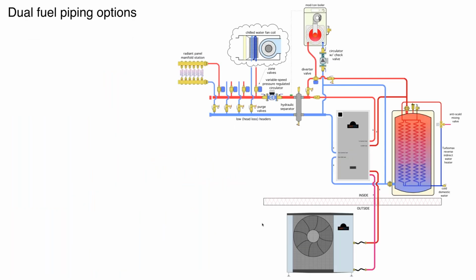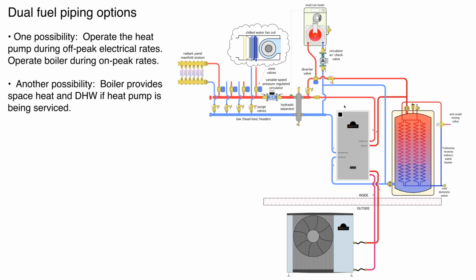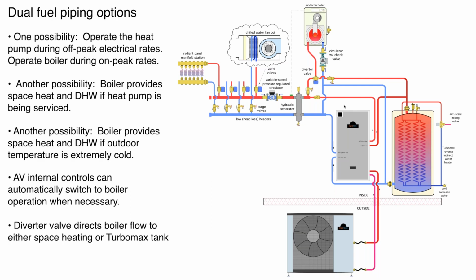Okay. Dual fuel. You can tie a boiler in with the heat pump. There are several ways to do it. I'll just go to the next slide, but first let's talk about these. Where do you want dual fuel? Well, you might have an existing boiler, or you might want something that could operate in a power outage where you may not have a generator large enough to operate the heat pump. Okay. You might have off-peak rates where you're going to favor the heat pump as the heat source when you have low-cost electricity. And if you have high peak rates, go to some other type of heat source during those periods. You know, it could be gas, it could be propane, possibly even fuel oil.